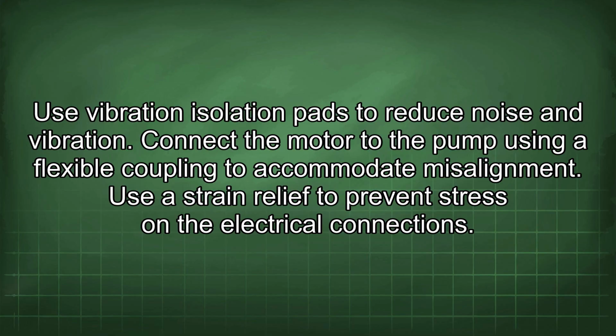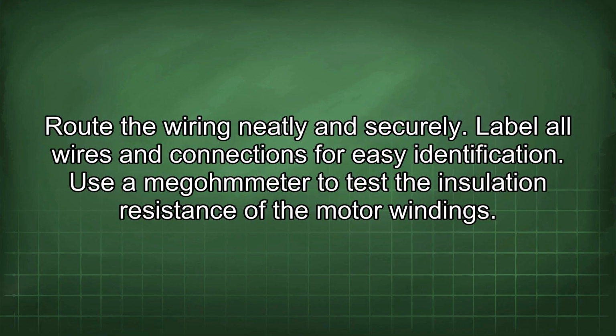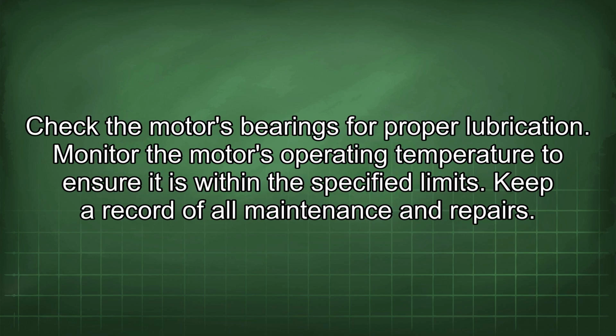Use the strain relief to prevent stress on the electrical connections. Route the wiring neatly and securely. Label all wires and connections for easy identification. Use a megohmmeter to test the insulation resistance of the motor windings. Check the motor's bearings for proper lubrication. Monitor the motor's operating temperature to ensure it is within the specified limits. Keep a record of all maintenance and repairs.